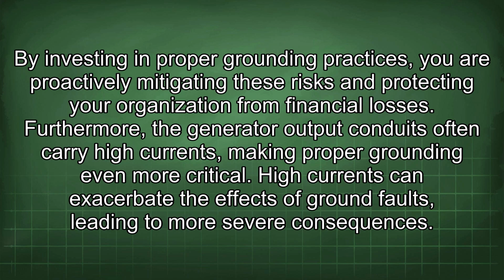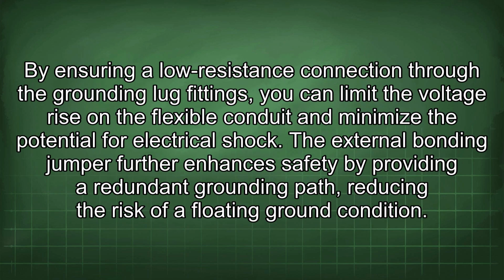Furthermore, the generator output conduits often carry high currents, making proper grounding even more critical. High currents can exacerbate the effects of ground faults, leading to more severe consequences. By ensuring a low resistance connection through the grounding lug fittings, you can limit the voltage rise on the flexible conduit and minimize the potential for electrical shock. The external bonding jumper further enhances safety by providing a redundant grounding path, reducing the risk of a floating ground condition.